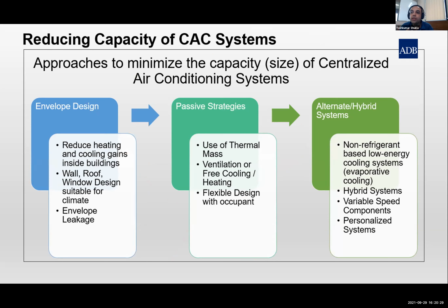So the first step is how do we reduce the capacity of the centralized air conditioning system? These are the 3 pillars that the earlier webinar in this series focused on in terms of the energy efficiency of systems in buildings. A very important element is envelope design. You need to reduce the heating and cooling gains inside the buildings through a good envelope design. That includes good wall, roof, and window design that's suitable for the climate. You can't use one size fits all; you have to select the right design for the right climate. You have to minimize envelope leakage. By envelope design, you are reducing the capacity of the system and the need for refrigerant. The quantity of refrigerant goes down because the capacity of the system is going down.